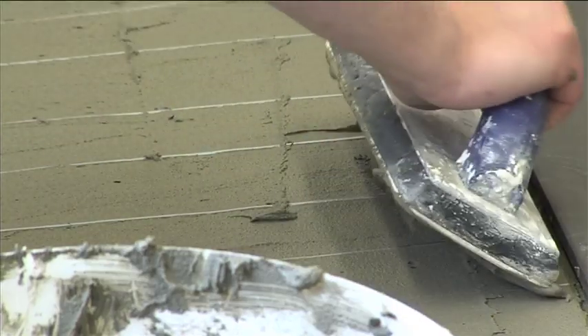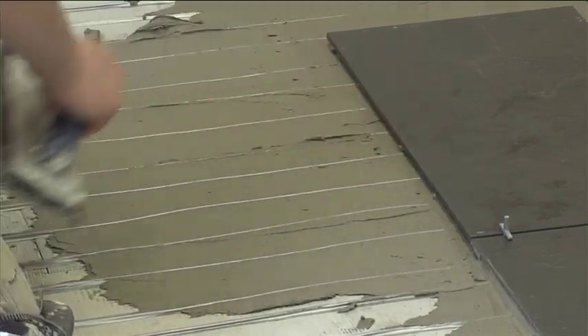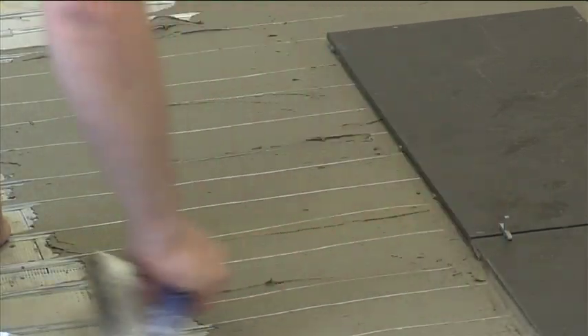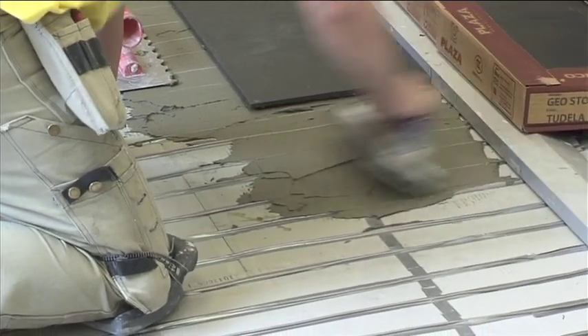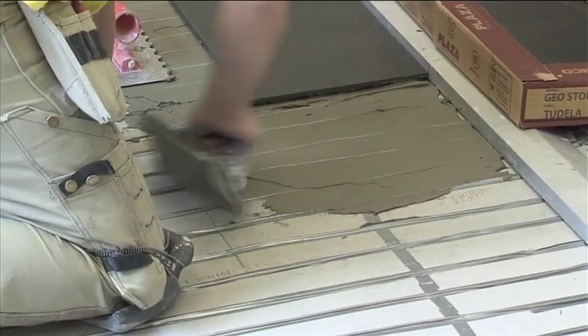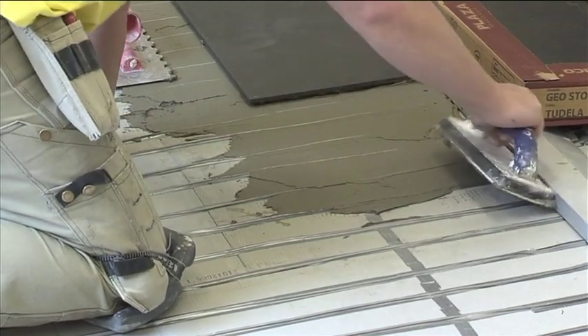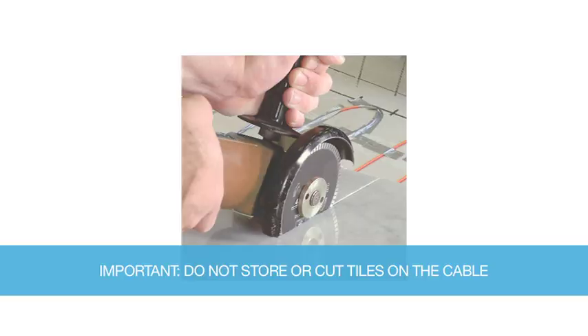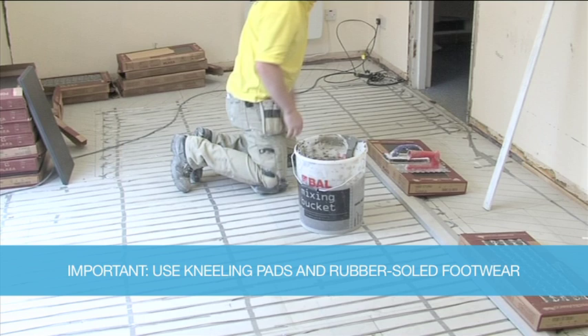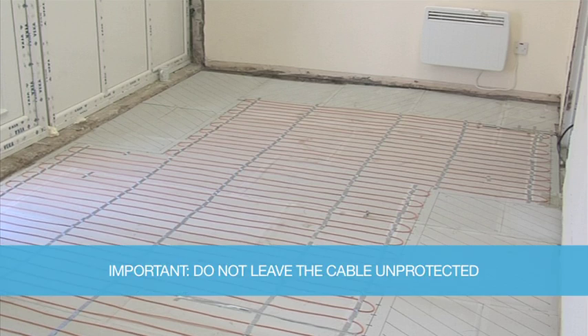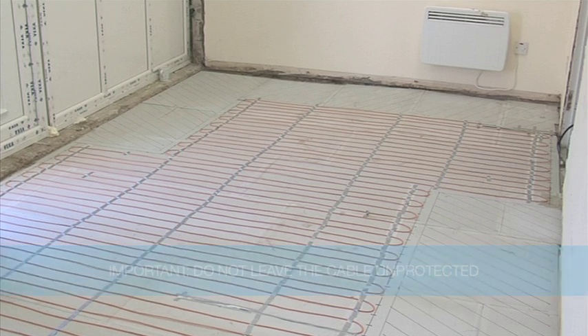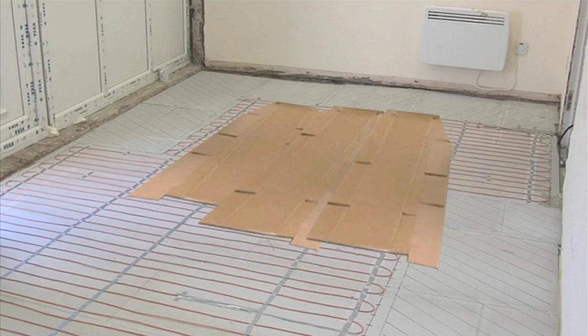The heating cable is robust, however care must be taken not to damage it during tiling. Use a piece of carpet or thick cardboard as a protective layer, or use a kneeling board to prevent damage to the heating cable from footwear or knees during the tiling process. Do not store or cut tiles on the heating cable. Use kneeling pads and rubber-soled footwear. Do not leave the cable unprotected if the finished floor is not tiled immediately. Cover with protective material like thick cardboard and minimise foot traffic in the area.